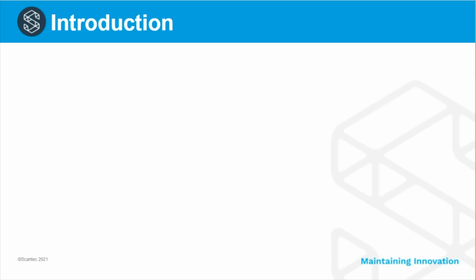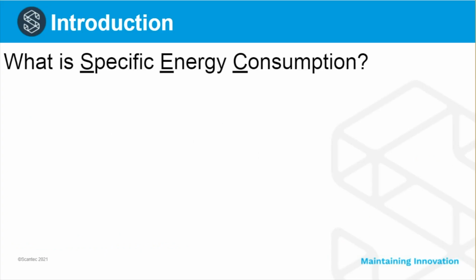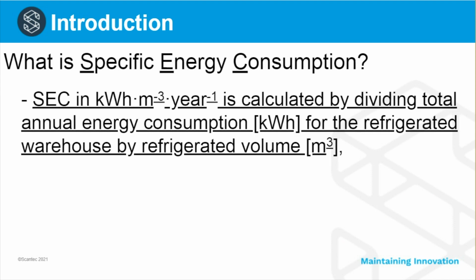Now, this is the business part, if you like, of the presentation. For those of you who didn't quite follow what I was saying before about specific energy consumption, I'll just explain here what that means. If you imagine you're a cold store operator and you know what the annual energy consumption of the cold store is, either from the utility or from the SCADA system, you take that annual energy consumption of the ammonia plant measured in kilowatt hours, and you divide that by the refrigerated volume in cubic meters. That way you get the specific energy consumption in kilowatt hours per cubic meter per year. This is a very widely used metric for comparing the energy efficiency of refrigerated warehouses without blast freezing.